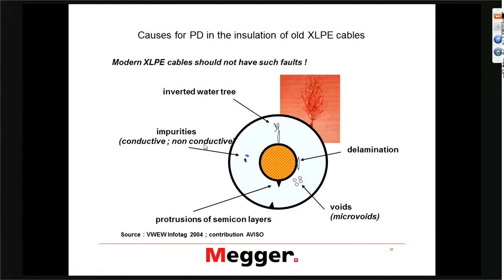In XLPE cables, we have older XLPE cables which were not as well quality controlled — you might have inclusions or foreign objects. Whenever you have that in a cable, you increase the dielectric stress or electrical field at that point, creating more stress in the insulation which ultimately creates issues. You might have impurities, voids, or — a very, very bad situation — delamination between the insulation and the semi-con. If you bend the cable too strongly, the insulation will separate from the semi-con and you might get an air pocket in between, and that's basically the end of the cable.